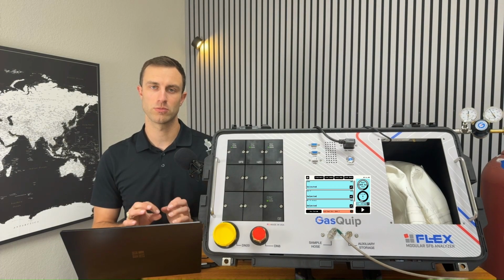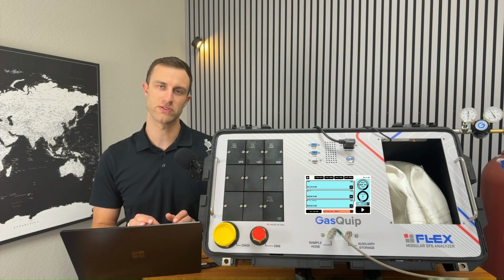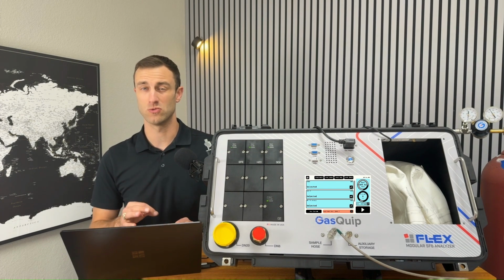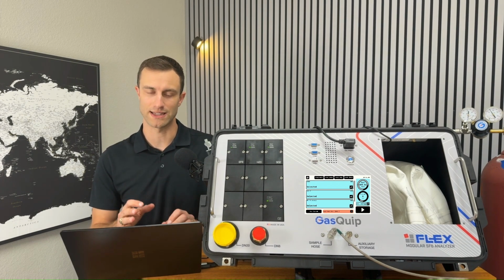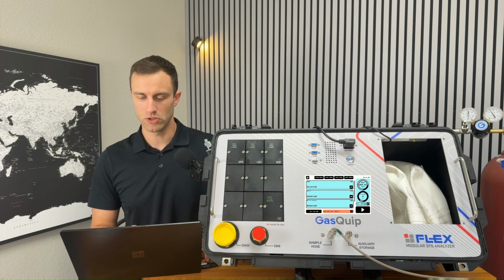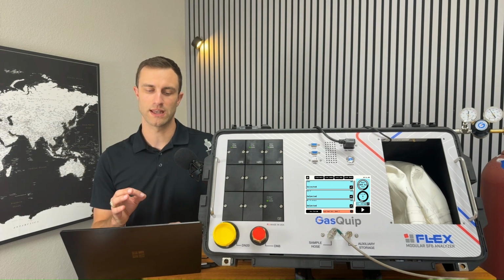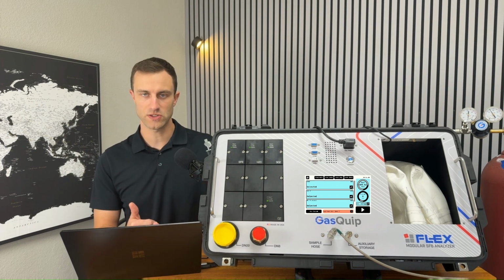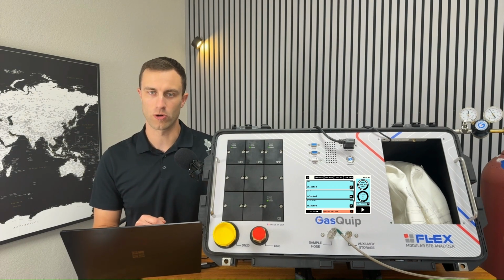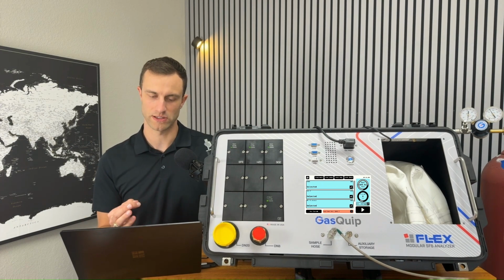Now let's talk about troubleshooting your test measurements, for when you get results that you didn't expect. The two that are most common would be getting an H2O reading that is higher than expected, so wetter gas than you expected to test, or an SF6 purity reading that is lower than you were expecting to get.